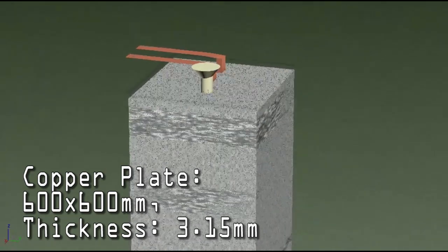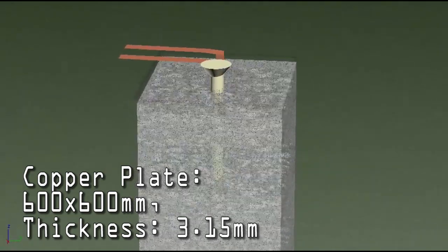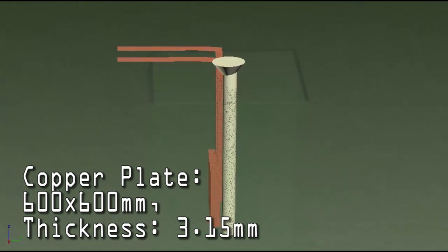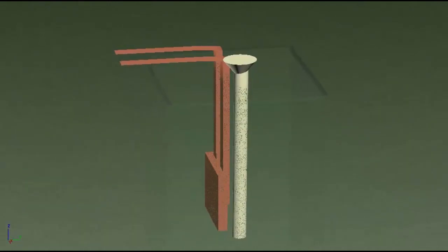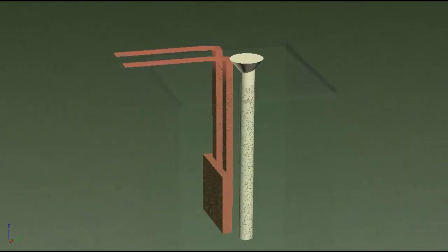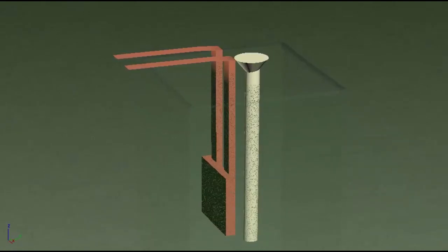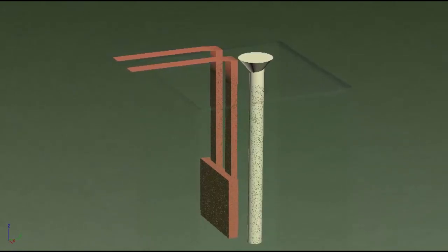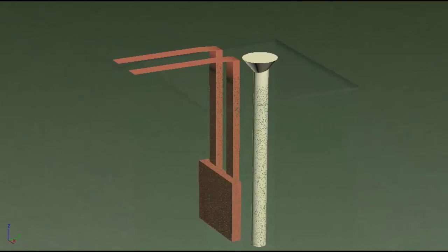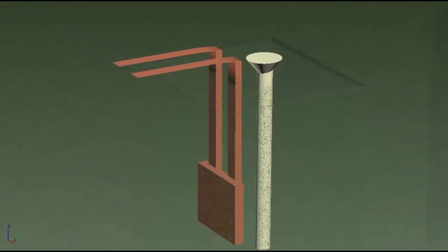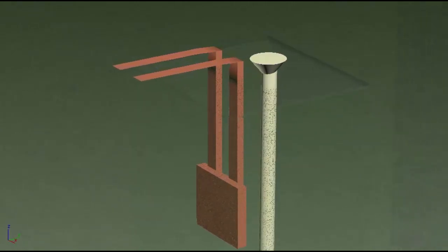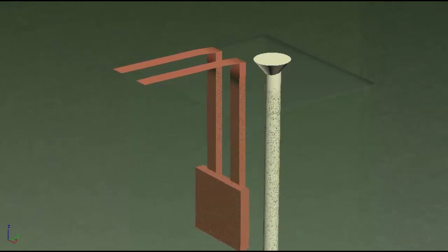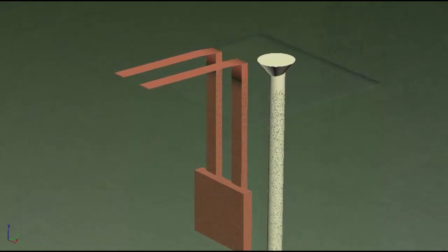Two GI strips of size 550 mm by 6 mm are fixed to this copper plate as shown. These strips should preferably be welded to the copper plate.